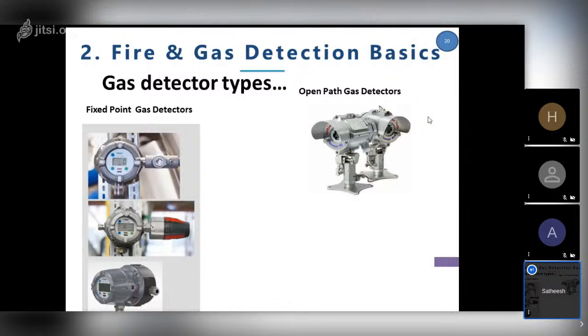Now, the next one is called open path gas detector, or line of sight, or beam detector. Here you can see the gas detector is like two pieces of equipment in one set, like a couple. One is called the transmitter, one is called the receiver. So you put a transmitter here and a receiver here. This entire length is open, but if any gas comes into this path, it is able to detect the gas, mainly clouds and big leaks. So this cannot replace the point detector. They are complementing each other.